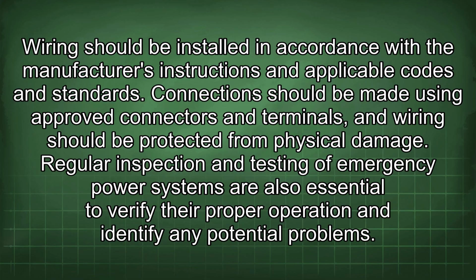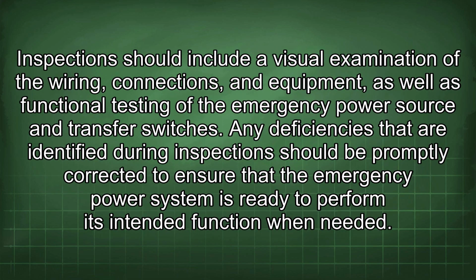Regular inspection and testing of emergency power systems are also essential to verify their proper operation and identify any potential problems. Inspections should include a visual examination of the wiring, connections, and equipment, as well as functional testing of the emergency power source and transfer switches. Any deficiencies that are identified during inspection should be promptly corrected to ensure that the emergency power system is ready to perform its intended function when needed.